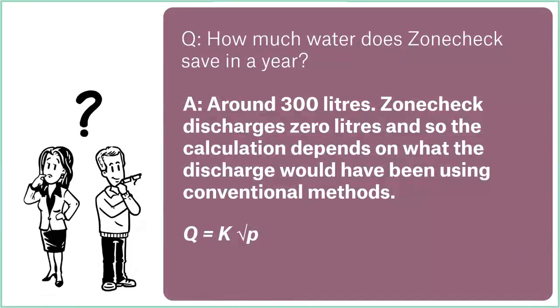So it's around 300 litres per test. Okay, so remember, zone check is testing flow switches. If you don't have a zone check installed, then you would need to use manual methods, and that means opening the test line to discharge water to actually test your flow switch. So the amount of water that zone check saves, so zone check uses no water. So really the question is, how much does it save in comparison to manual methods?